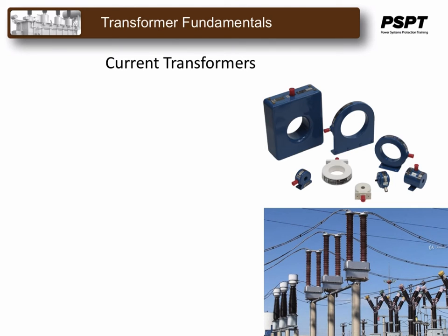In a current transformer, the secondary current is determined entirely by the current flowing in the primary system and not by its own secondary load, which is usually referred to as the burden. However, the voltage across the secondary load or burden is very much dependent on the secondary load. Since the current in the secondary is constant if the primary current is constant, then according to Ohm's law, the higher the impedance of the secondary load, the higher the voltage across the load will be. If the secondary load is very high, say open circuited, then the voltage will rise accordingly and could result in a very dangerous condition.